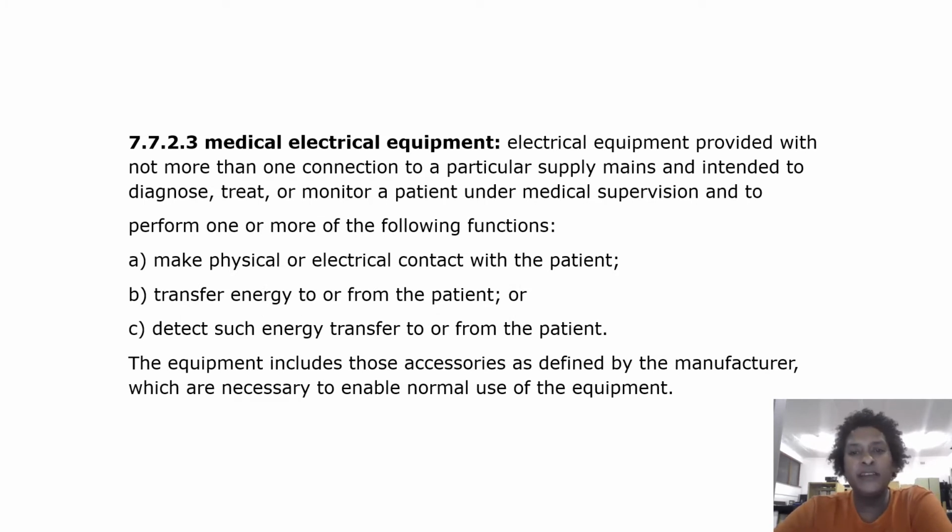Medical electrical equipment. Electrical equipment provided with not more than one connection to a particular supply mains and intended to diagnose, treat, or monitor a patient under medical supervision and to perform one or more of the following functions: make physical or electrical contact with the patient, transfer energy to or from the patient, or detect such energy transfer to or from the patient.